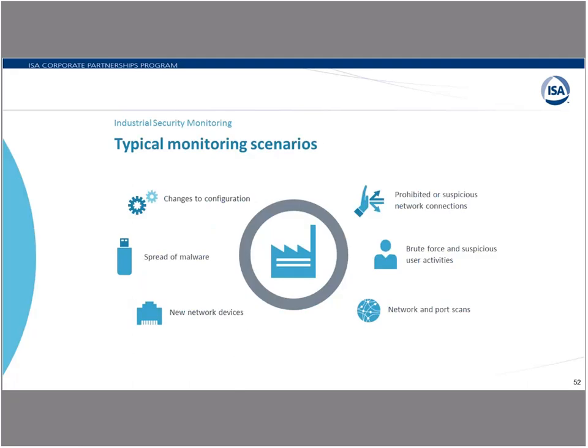Some of the typical monitoring scenarios we feel are important include: changes of configuration—production areas are often unmonitored, with many outstations, making it hard to detect configuration changes; brute force and suspicious user activities—for example, is it normal for a user to be sending data out of country every morning at 2 a.m.?; spreading of malware; and new network devices—nine times out of ten you'll never notice when a new network device has been placed in your network unless you have a monitoring scenario; as well as prohibited or suspicious network connections and port scans.